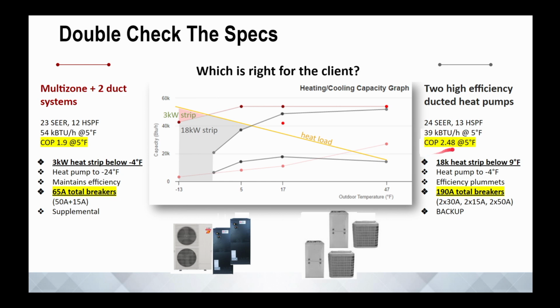Now, if you look at the COP, that's a measure of efficiency. It's energy output over energy input. Sorry for the technical stuff, but we're going to get into a little bit more of this in a couple minutes. But the efficiency ratio is higher, 2.48 at 5 degrees. Well, that's a pretty efficient system at 5 degrees. This one is only 1.9, so 190% efficient at 5 degrees. This one is 248% efficient at 5 degrees. Well, that sounds pretty good. Why don't we go with that?